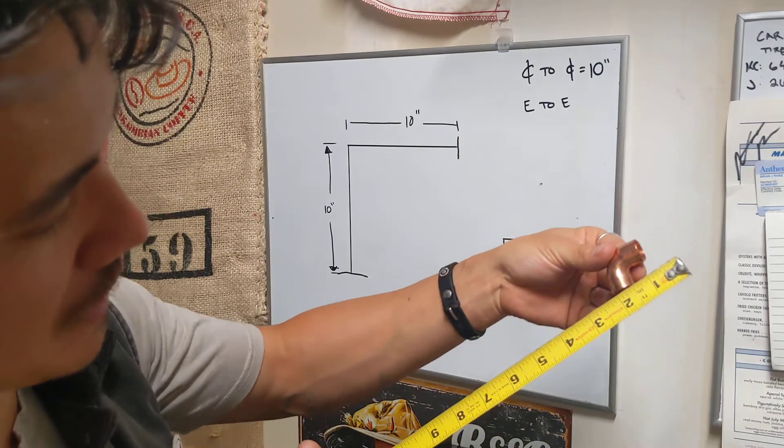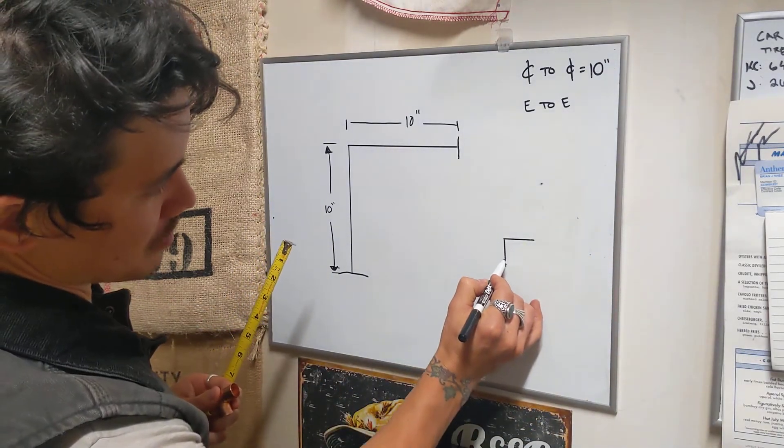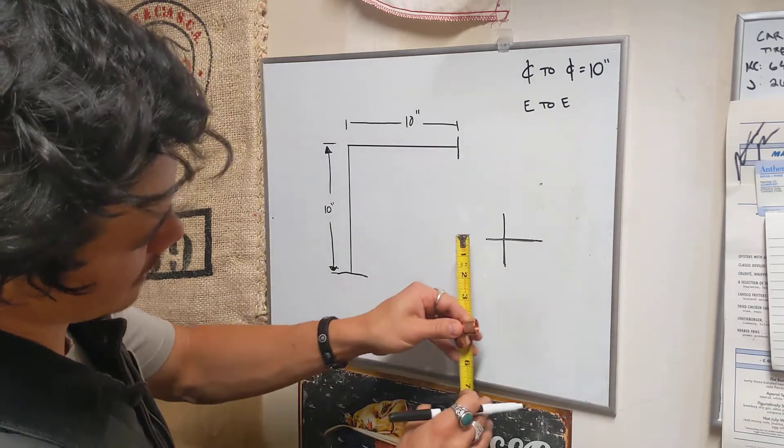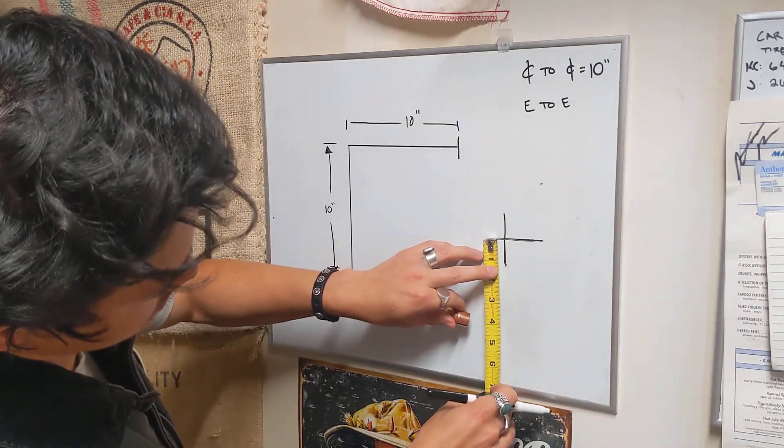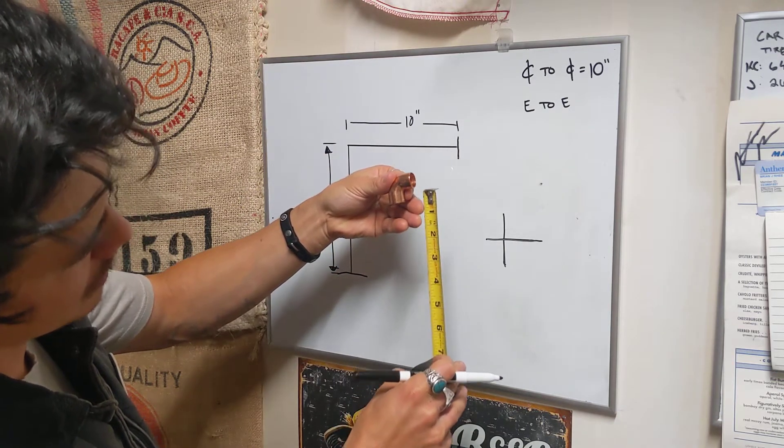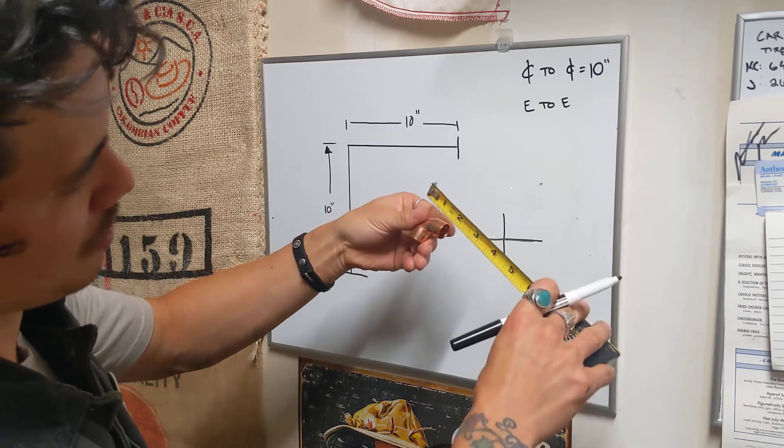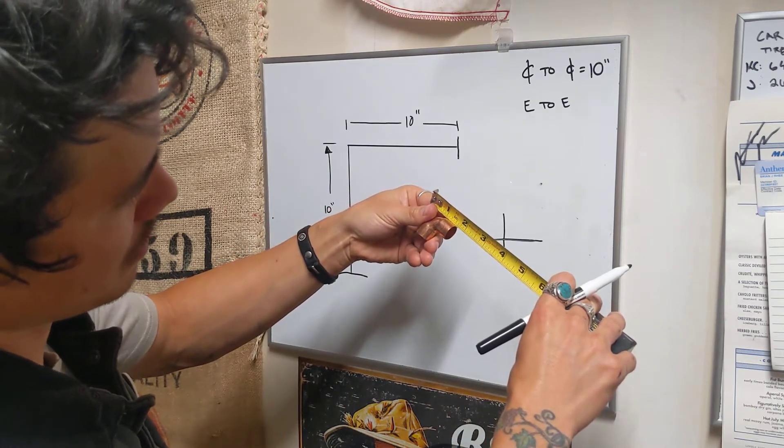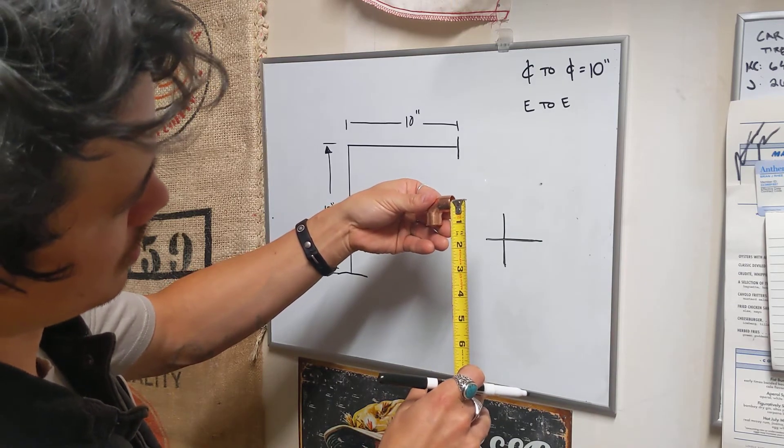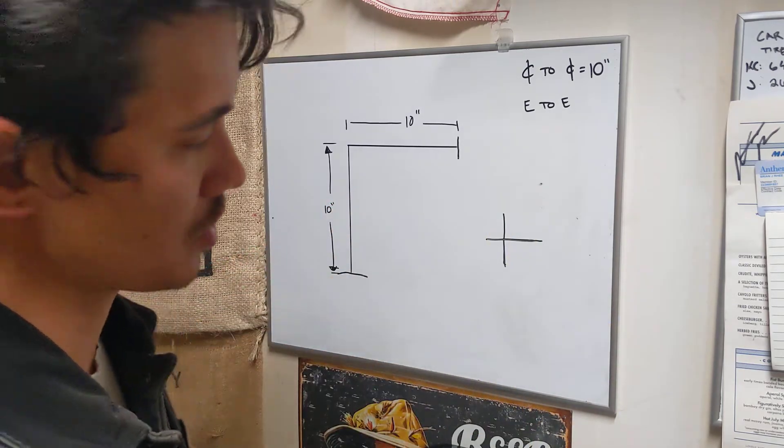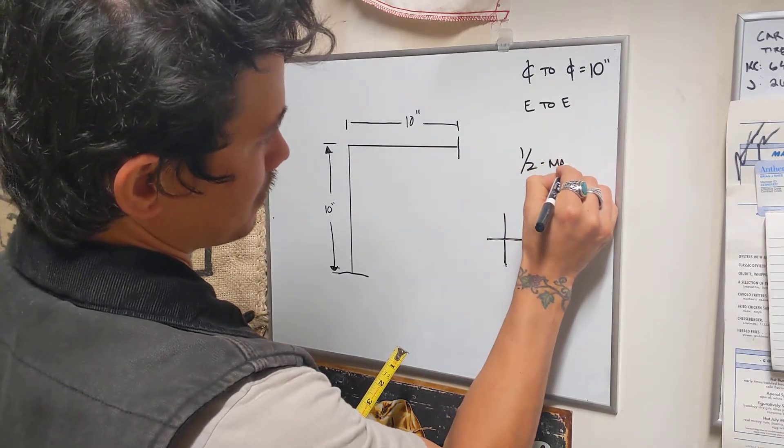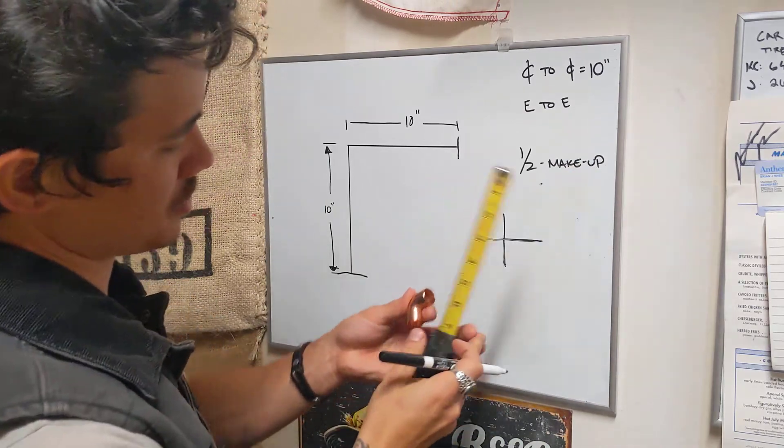So we're measuring from this line of the fitting, center line here to center line here. So what we're looking at is if you go from here to here you're looking at about an inch. Now you have to take off your makeup though and if your makeup let's call it half an inch, that leaves you half an inch. So half an inch of makeup is that fitting that your pipe goes into.